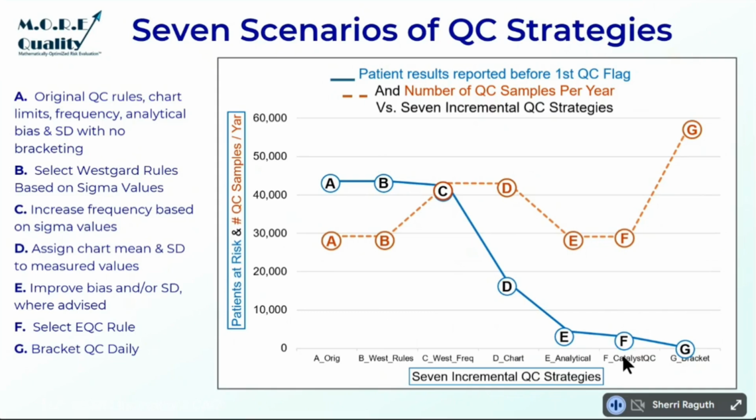All right, watch this. She says, by putting the right mean, quote unquote, into your QC chart, is it the manufacturer provided one, or are we missing something? You are missing something, and bless your heart for asking. The purpose of the quality control chart is to tell you when the method changes. That is the only thing a quality control chart could do.